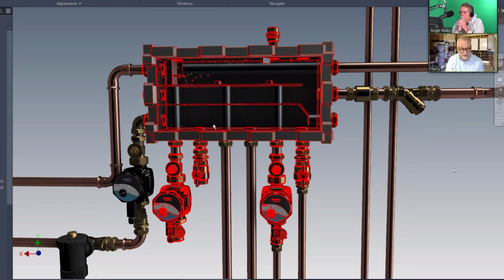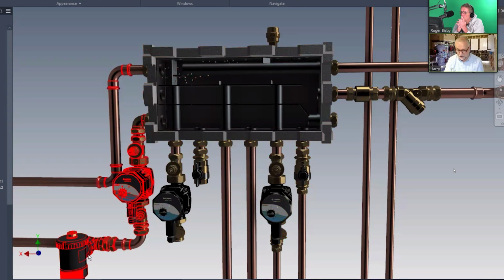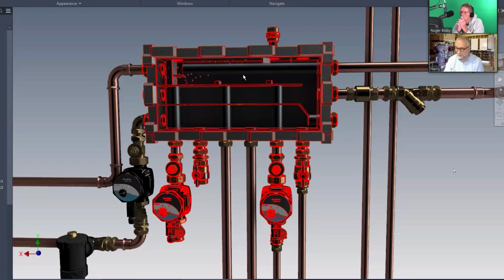Do you know the most perfect heating system, if you think of this? If I get a barrel of water, right, and I put a pipe leaving the top of the barrel, head off around my house, and it comes back to the barrel, and I have a fire under the barrel, and I'm heating the barrel of water, and I have a pump pumping from the barrel away and around the system, and it comes into the bottom of the barrel, the fire heats it again, goes up to the top, rises away. Well, that's basically what we have. We have a container that has water in it. The water is being taken from the end of the container, is being heated by something, and comes back into the top of the container. If the container is sealed, it just means that you have an artificial volume, an air container that expands and contracts as the water contracts. And if it has a tank, there's no difference between a sealed system and an open system, in that it's just somewhere for the water to expand to.